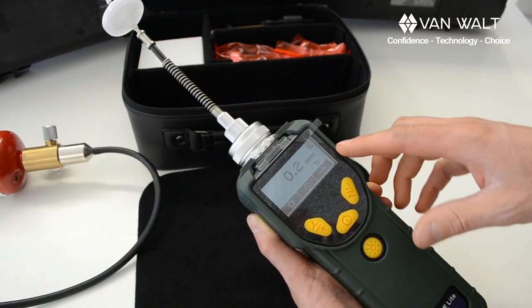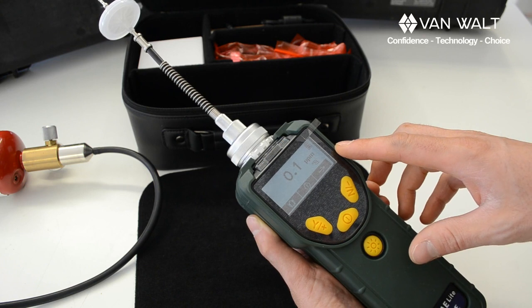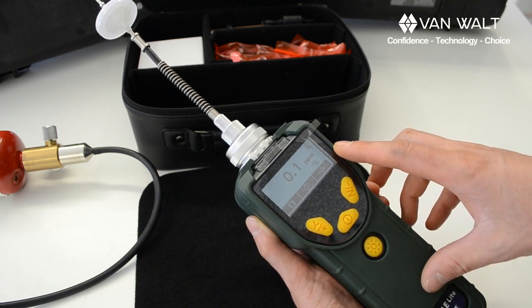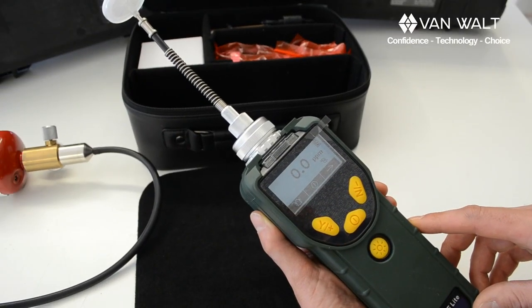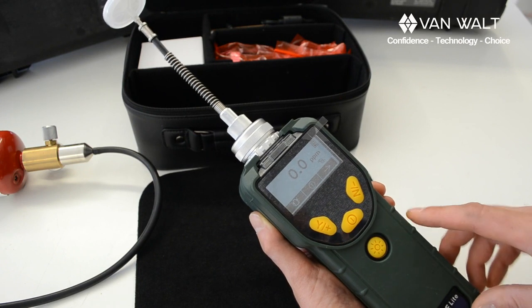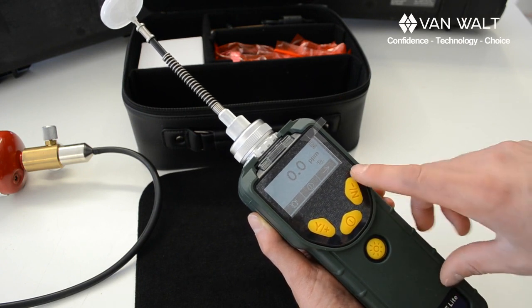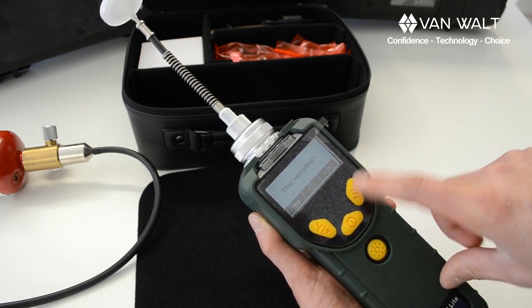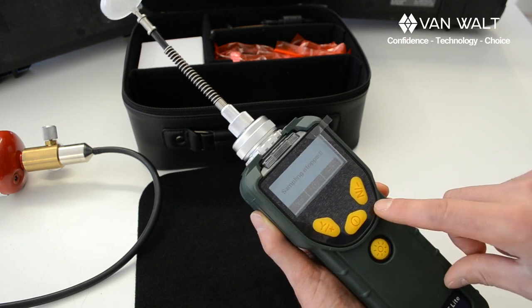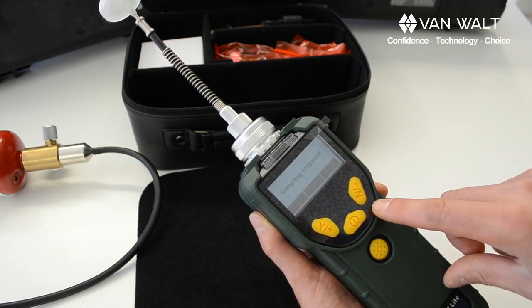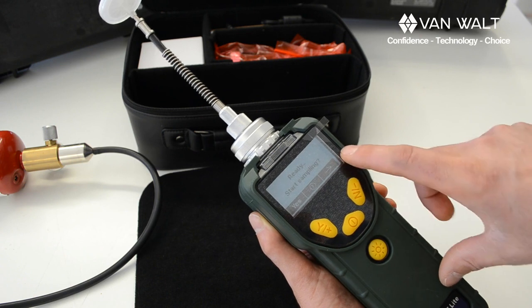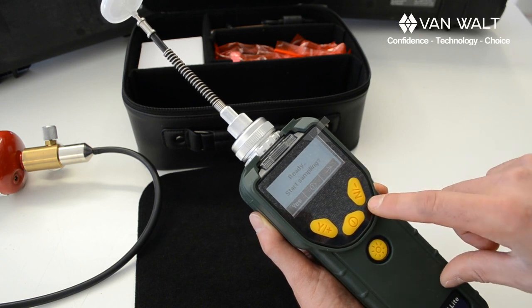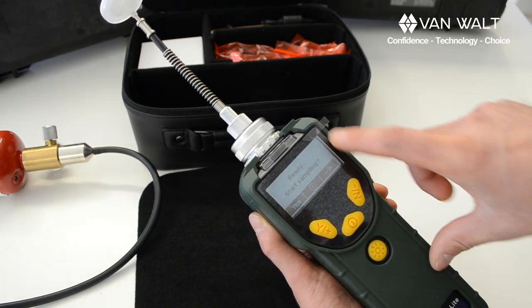And the recovery is pretty good. It's going to recover to near as makes no difference, 0 ppm. If we're not happy about the calibration, we can go into the calibration mode. So I'm just going to press right, stop sampling, yes. And so it'll go back to the normal start screen. Yes, I'm ready, start sampling.